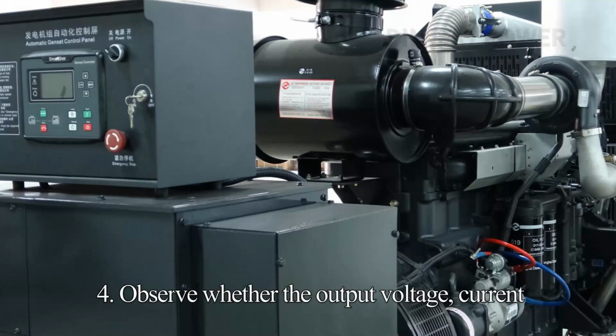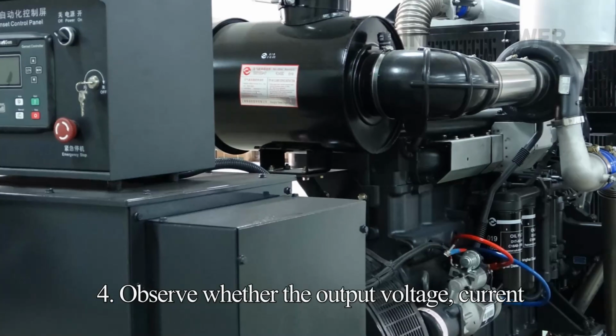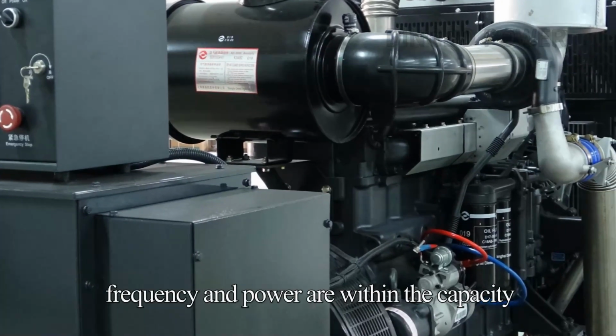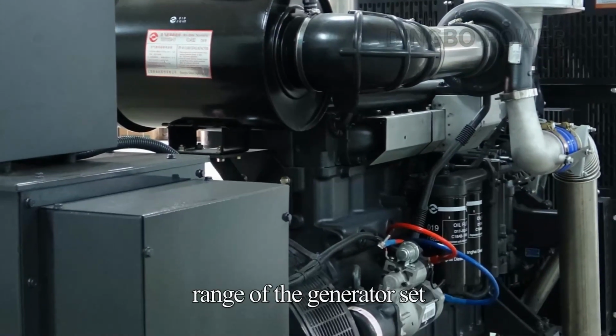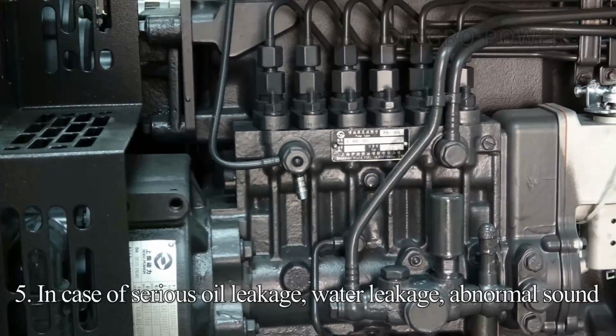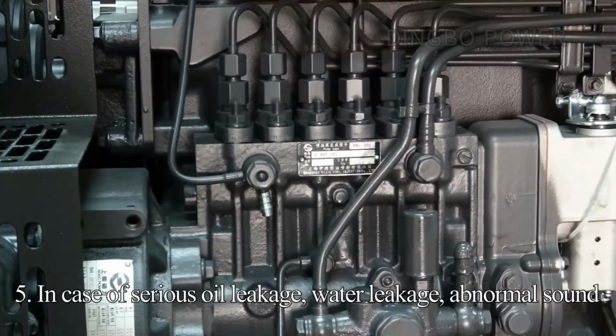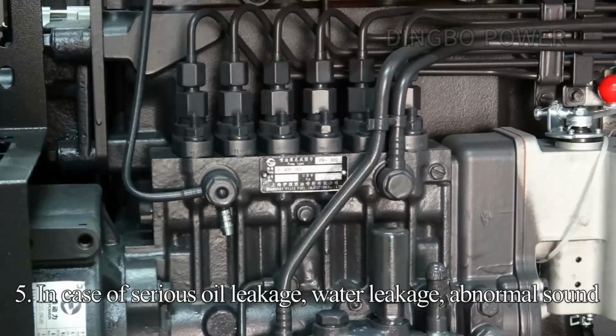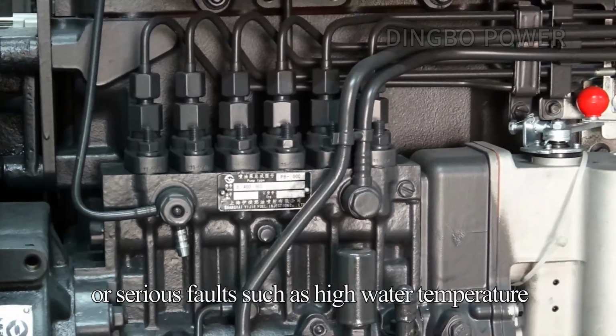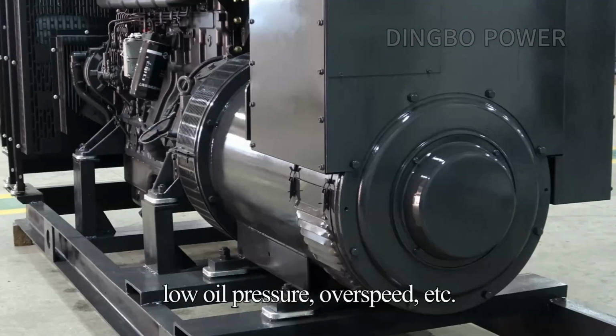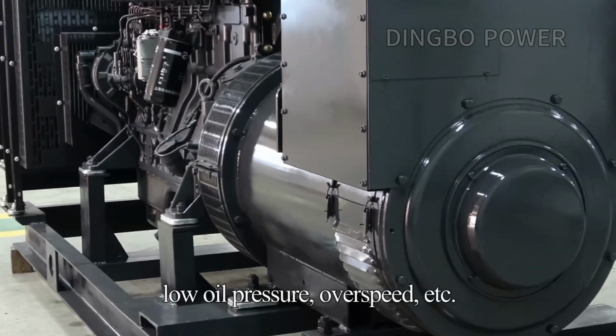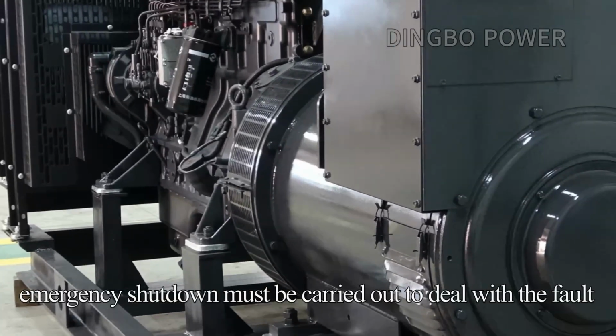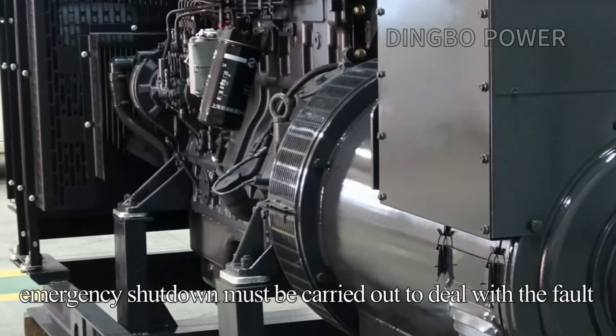4. Observe whether the output voltage, current, frequency and power are within the capacity range of the generator set. 5. In case of serious oil leakage, water leakage, abnormal sound, or serious faults such as high water temperature, low oil pressure, or overspeed, an emergency shutdown must be carried out to deal with the fault.